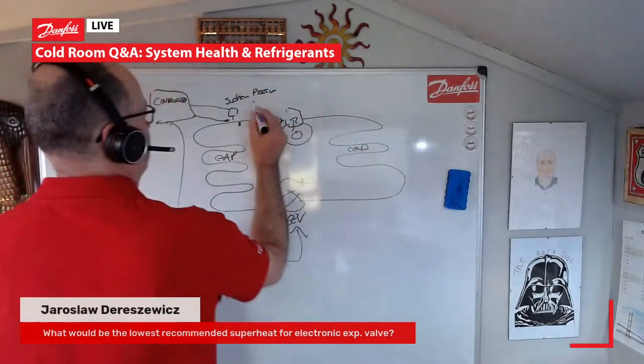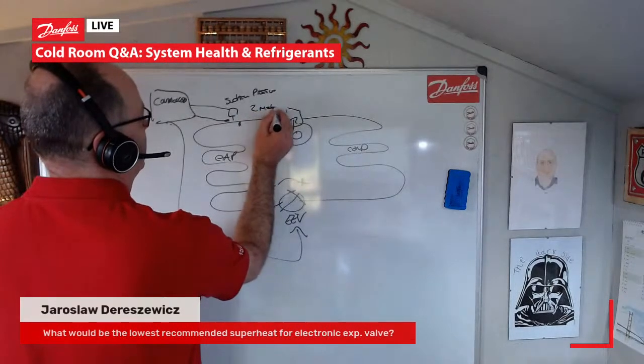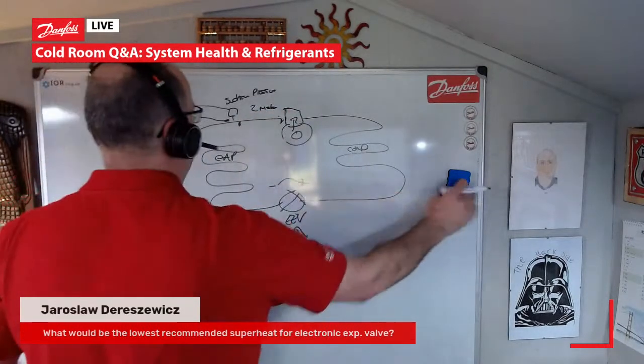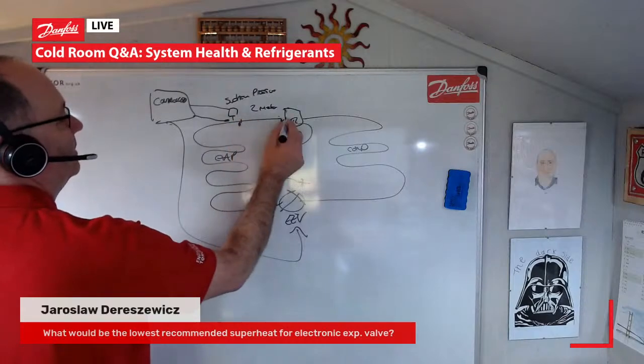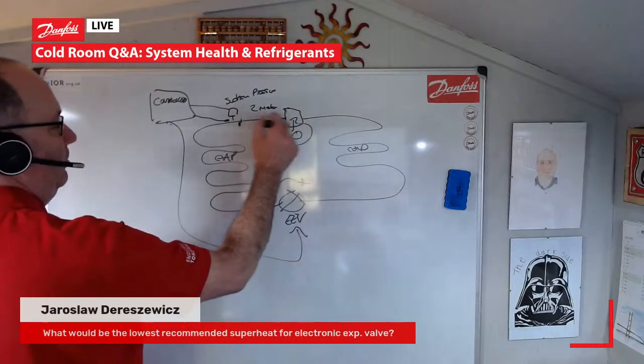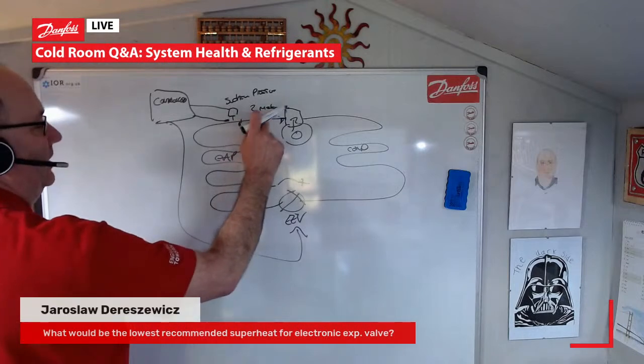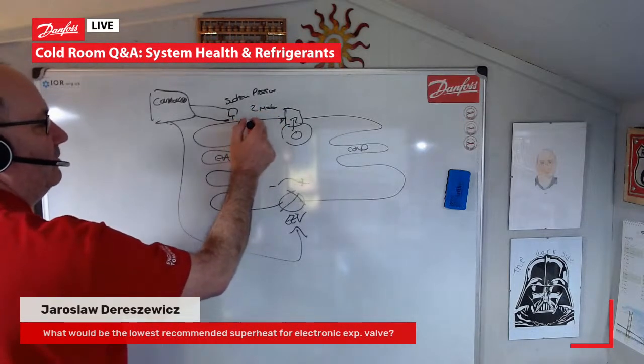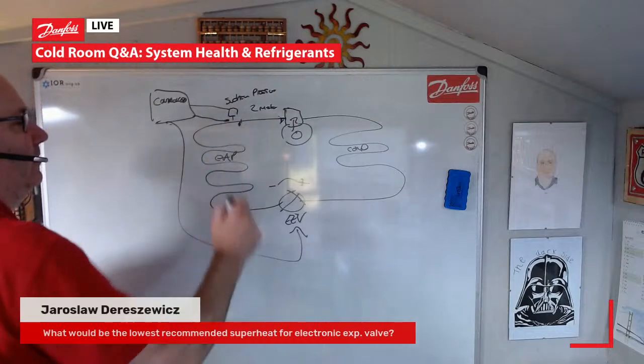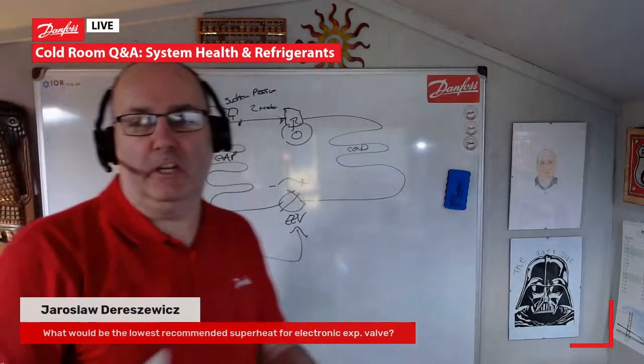If that was, let's go daft, 2 meters, you've only got 2 meters between the exit of your evaporator and your machine. So you're not going to pick up much heat externally in that 2 meters. So you've really got to look after your superheat on that evaporator. But in general terms, if we're talking electronic expansion valve, then 6K, I wouldn't really go any lower than that. If we're talking mechanical, yeah, 8, 9, somewhere around there, I would be quite happy with that. So I hope that answers that question.